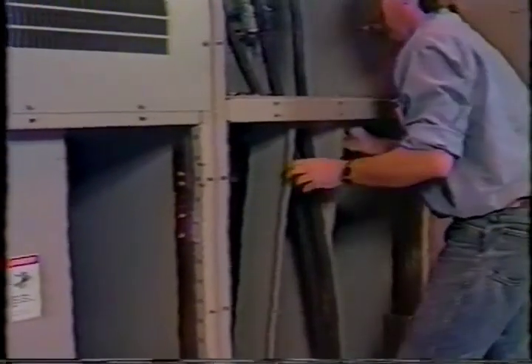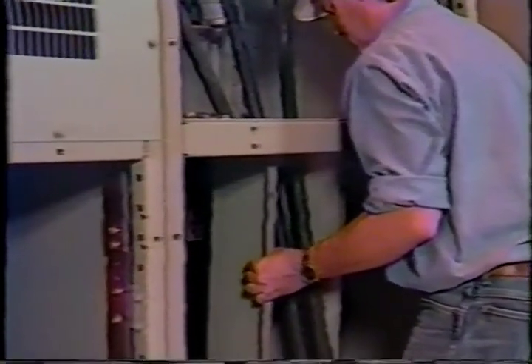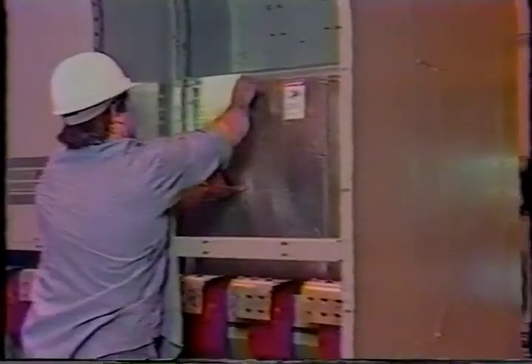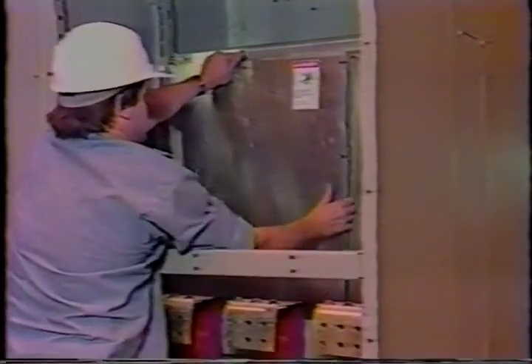A good and reliable ground connection is necessary for every switchgear installation. It should be of sufficient capacity to take care of any abnormal condition that might occur on the system, and should be independent of the grounds used for any other apparatus. Metal-clad switchgear is designed so that internal compartments provide metal isolation between the circuit breaker compartment, the main bus, and the primary line terminations. Access to high voltage parts is provided by removable covers and barriers, which should not be removed unless the parts to be exposed are de-energized.